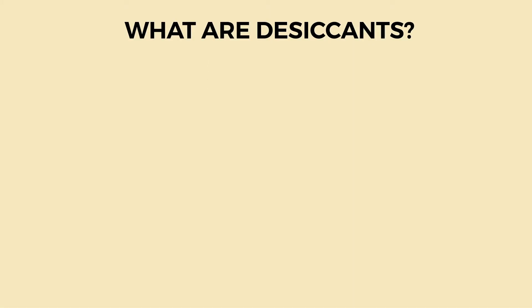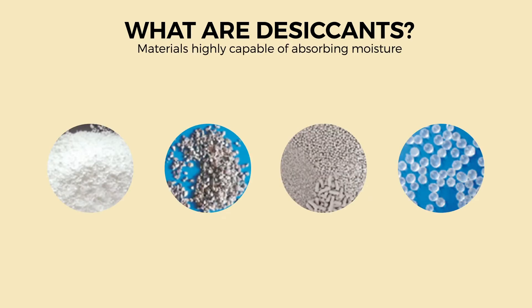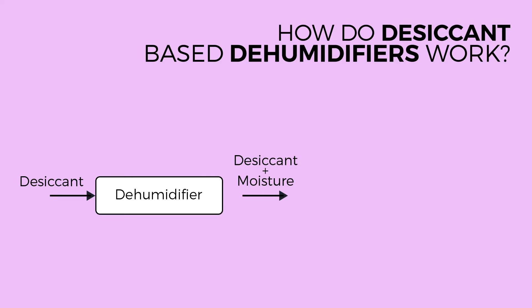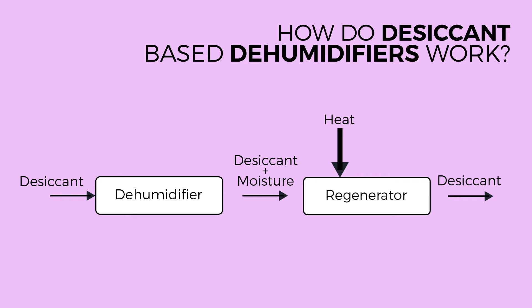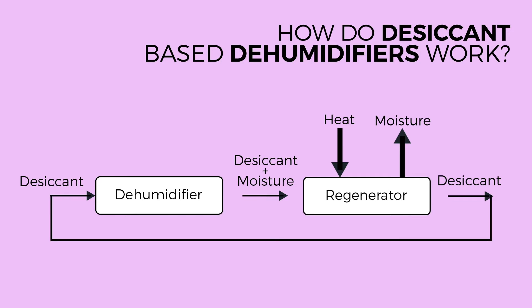Before we dive deep into the use of liquid desiccants, let us zoom out and understand what exactly this technology is. Desiccants are materials that are so hydrophilic that they are able to absorb moisture from air. These desiccant materials are used to dehumidify air, but once they have absorbed moisture from a system or from a room, the absorbed moisture needs to be removed. This is where solar heat, waste industrial heat, or heat from any other source would be used to drive the moisture out of the desiccant and into the environment. This is called regeneration, which dries the desiccant again so that it can be used for dehumidification, and the process can be repeated.